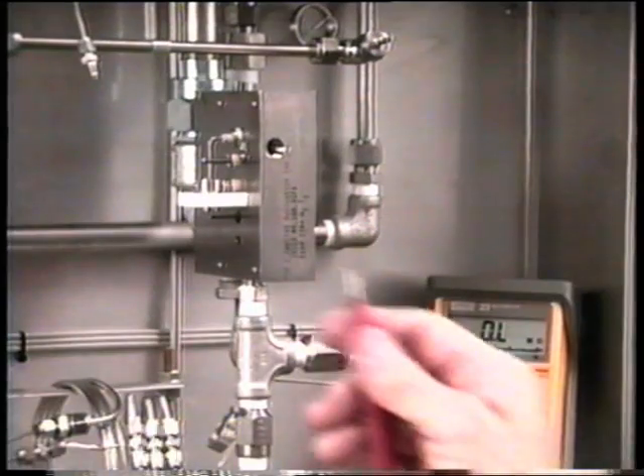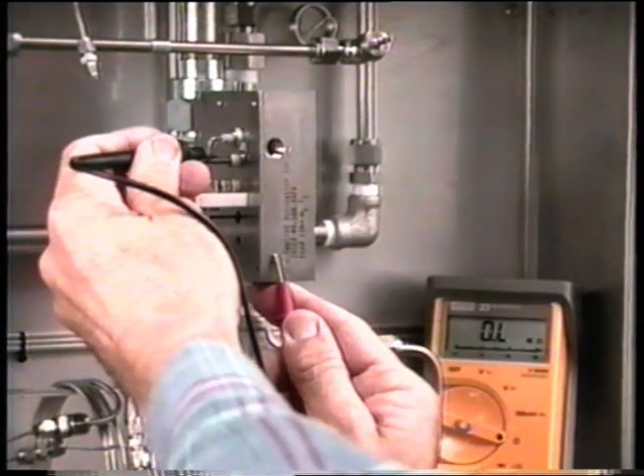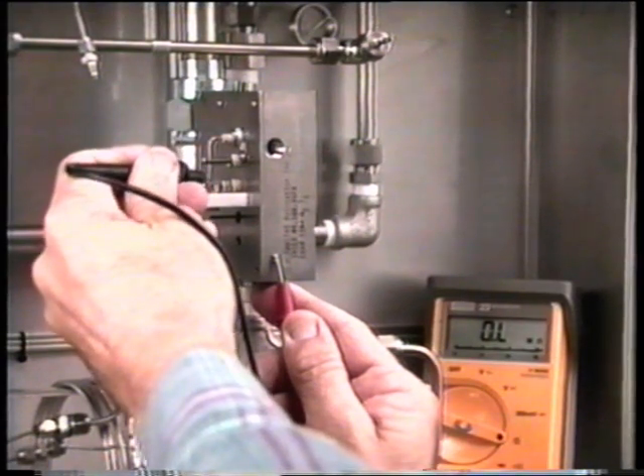Slide the electrode O-rings over the bias ignite and collector electrodes. Place a washer and nut on the bias ignite electrode. Tighten the nut and be sure the collector ring is centered in the baffle plate. Place a washer and nut on the terminal end of the collector electrode. Tighten the nut without turning the electrode. Measure the insulation resistance of the collector and burner tip.